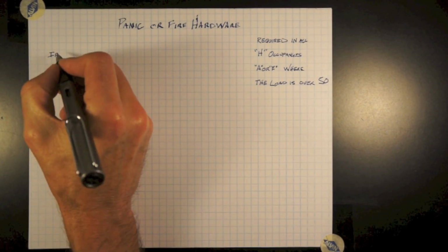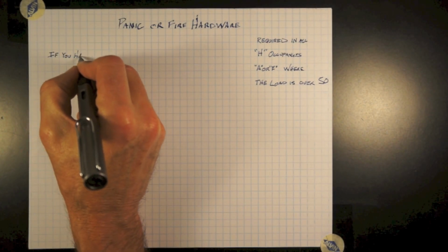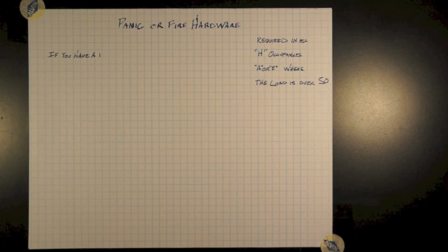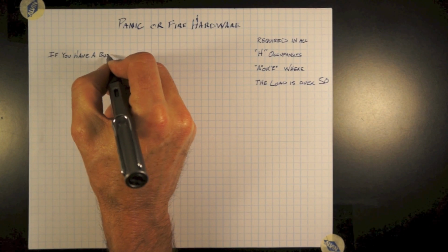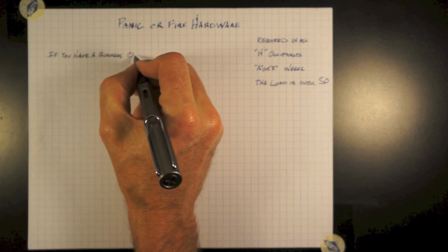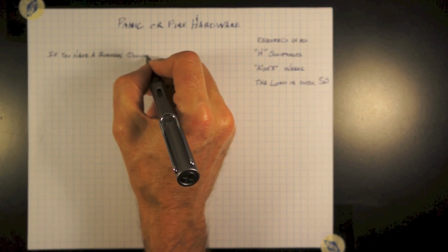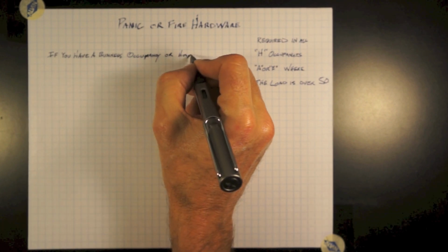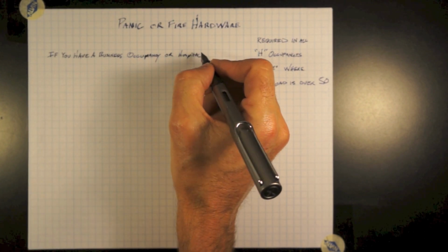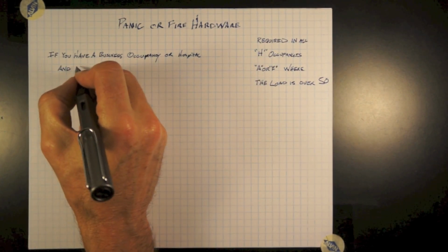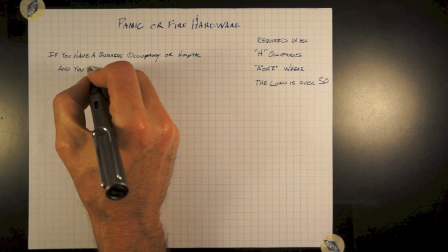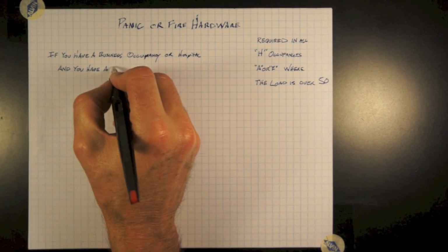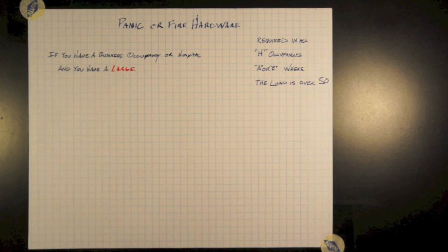So in business occupancies, they are not required unless you have a space such as an auditorium, a very large lobby space, or a break room where persons could gather that have an occupant load of over 50. This would trip it into the A or E occupancy type. I would suggest you view video number 6, occupant load, to understand how to calculate these spaces.